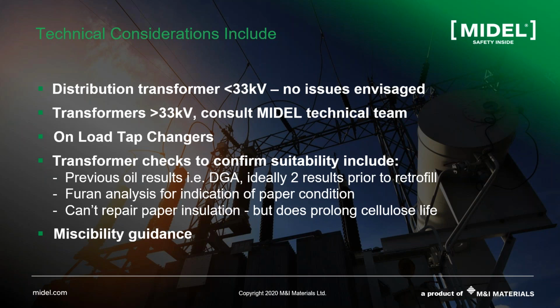Okay, so to select a transformer as a candidate for retrofill, we need to look first at the voltage class. Usually for distribution size transformers, any transformer lower than 33 kV, we do not expect any issues if we just replace the fluid. These transformers have lower stress in general, and so the insulation is based on the mechanical strength of the winding. If the transformer has a higher voltage class, higher than 33 kV, then please consult with us, because we need to review certain things to assess if this transformer is a good candidate for retrofill or not.